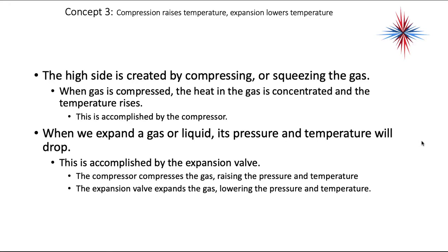Concept number 3, compression raises temperature, expansion lowers temperature. The high side is created by compressing or squeezing the gas. When gas is compressed, the heat in the gas is concentrated and the temperature rises. This portion is accomplished by the compressor. When we expand the gas or liquid, its pressure and temperature will drop. This is accomplished by the expansion valve. The compressor compresses the gas, raising the pressure and the temperature. The expansion valve expands the gas, lowering the pressure and the temperature.